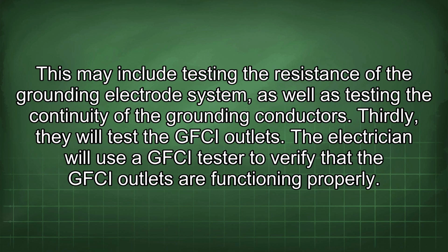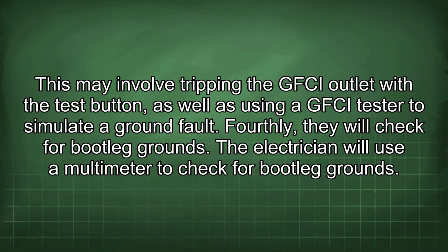This may include testing the resistance of the grounding electrode system, as well as testing the continuity of the grounding conductors. Thirdly, they will test the GFCI outlets. The electrician will use a GFCI tester to verify that the GFCI outlets are functioning properly. This may involve tripping the GFCI outlet with the test button, as well as using a GFCI tester to simulate a ground fault. Fourthly, they will check for bootleg grounds.